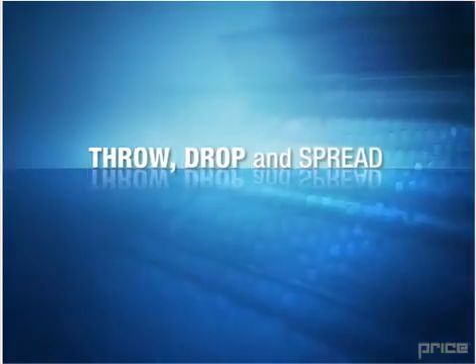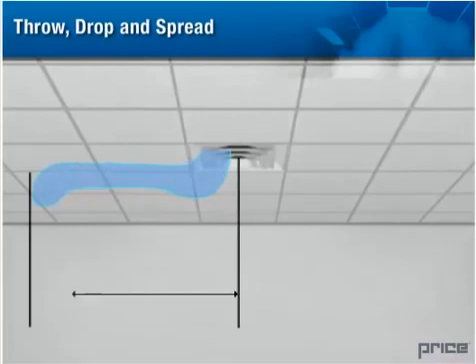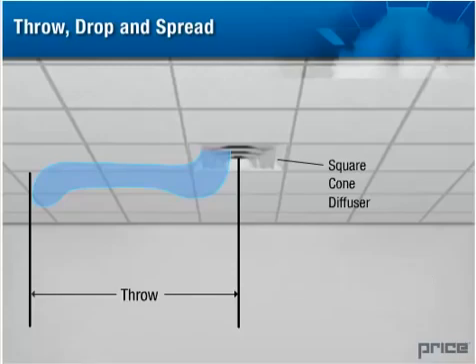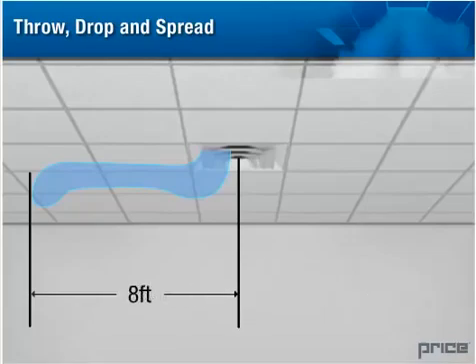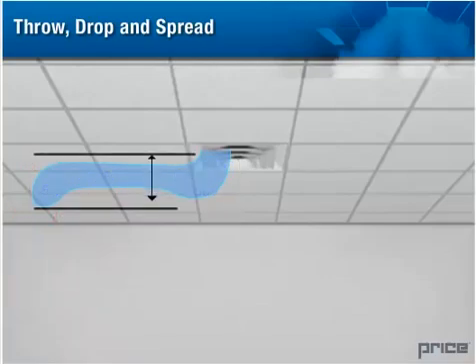Throw is the horizontal distance the supply air is projected out from the air outlet. We measure this distance for a specific air velocity. For example, this square cone diffuser has a throw of eight feet at a terminal velocity of fifty feet per minute — that is to say, the air is still moving at fifty feet per minute at a horizontal distance of eight feet from the diffuser.